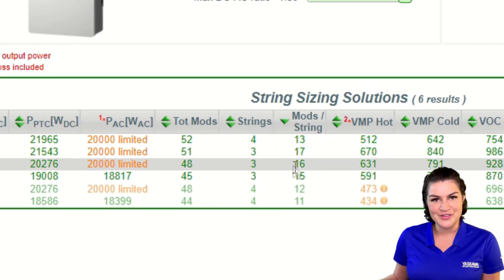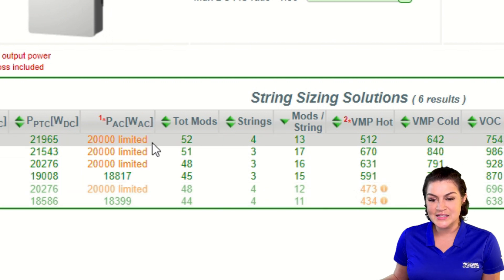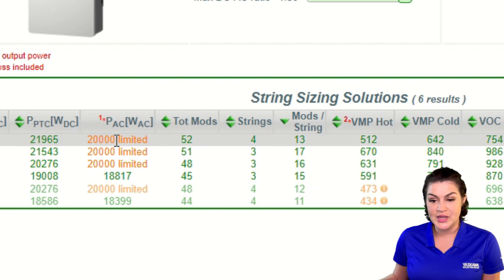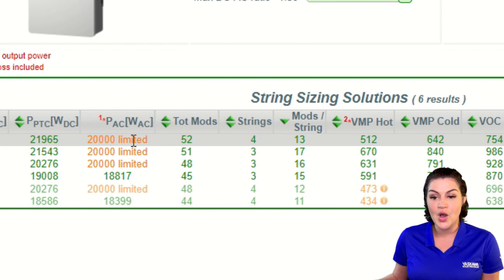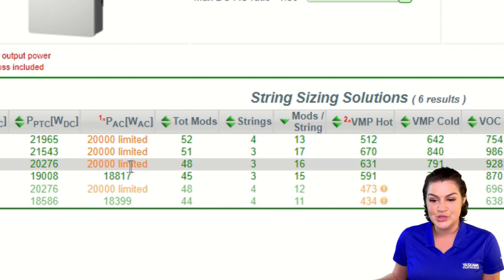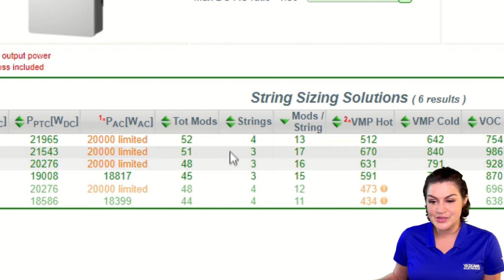Here are the different configurations that you can do. It does give you warnings — for example, in this configuration it looks like there could be some possible derating due to low string voltage. We also get a 20 kilowatt limit warning, but that's fine because we want that — we are sizing our DC higher than our AC, so we're expecting some clipping. This is just showing that some clipping would happen.